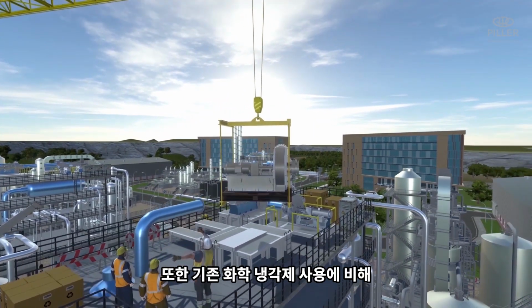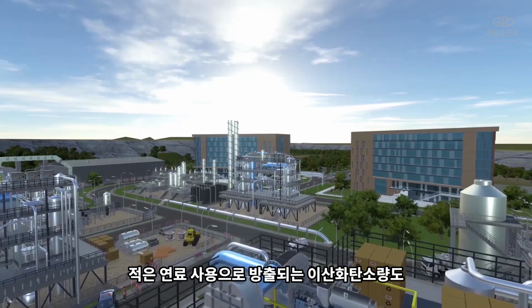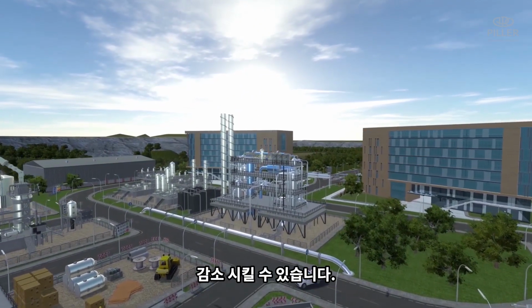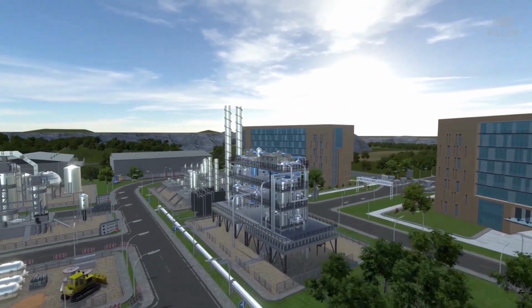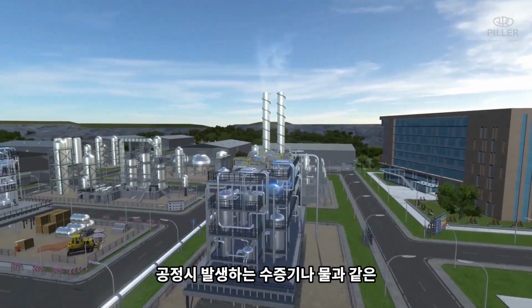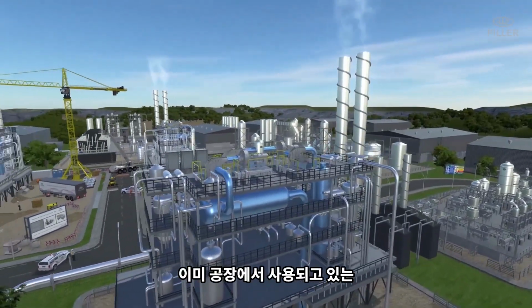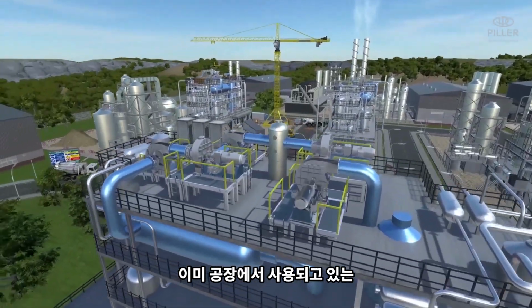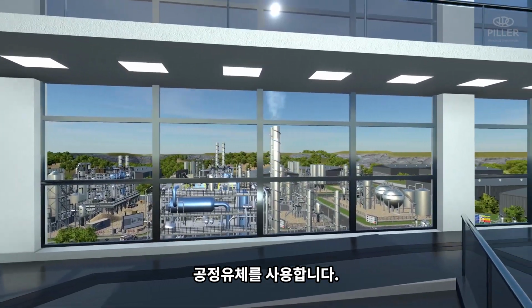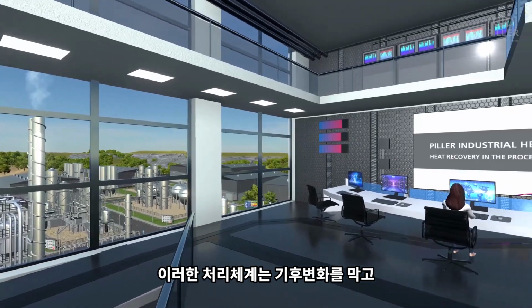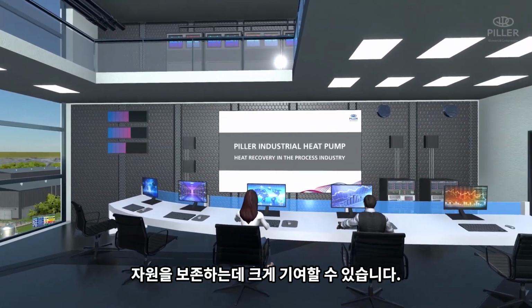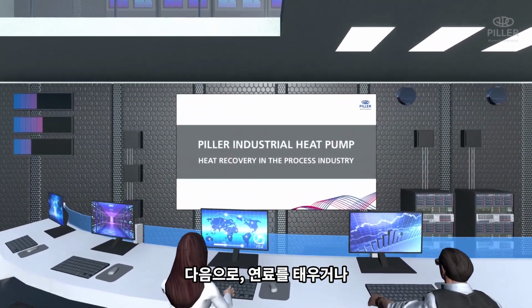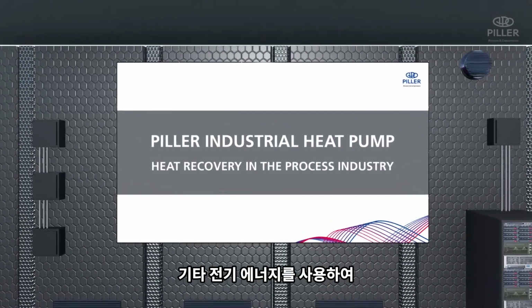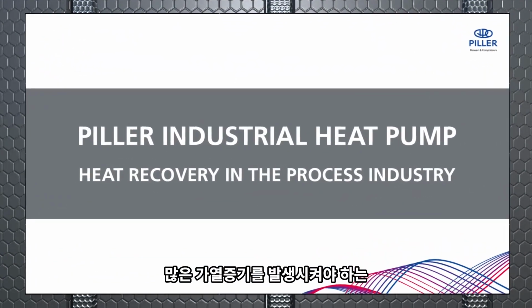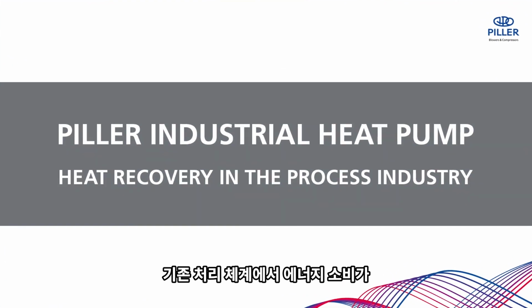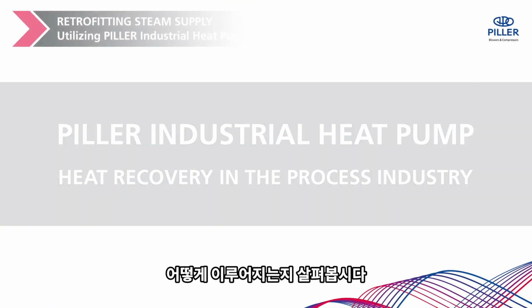By reducing fossil fuel use, CO2 emissions are reduced, and in contrast to conventional heat pumps that use chemical refrigerants, the PILLER industrial heat pump uses the existing process fluids, either the vapor from the process or water. The integration of the system thus contributes significantly to climate and resource protection. Let's take a look at the energy consumption in a conventional process with high demand for heating steam, which is generated by burning fossil fuels and some additional electrical energy.